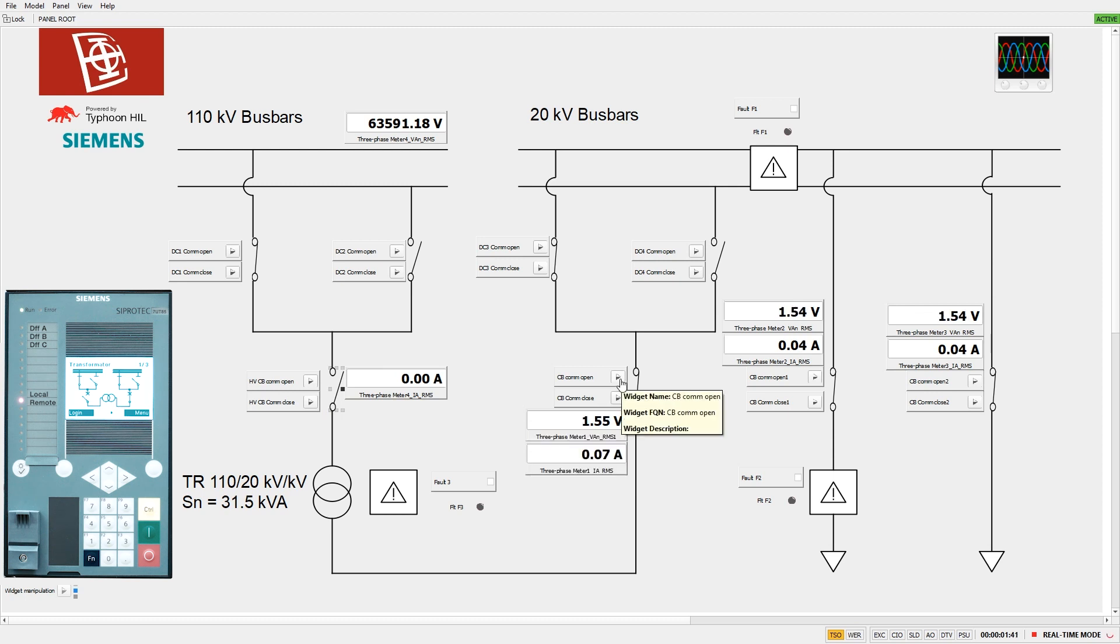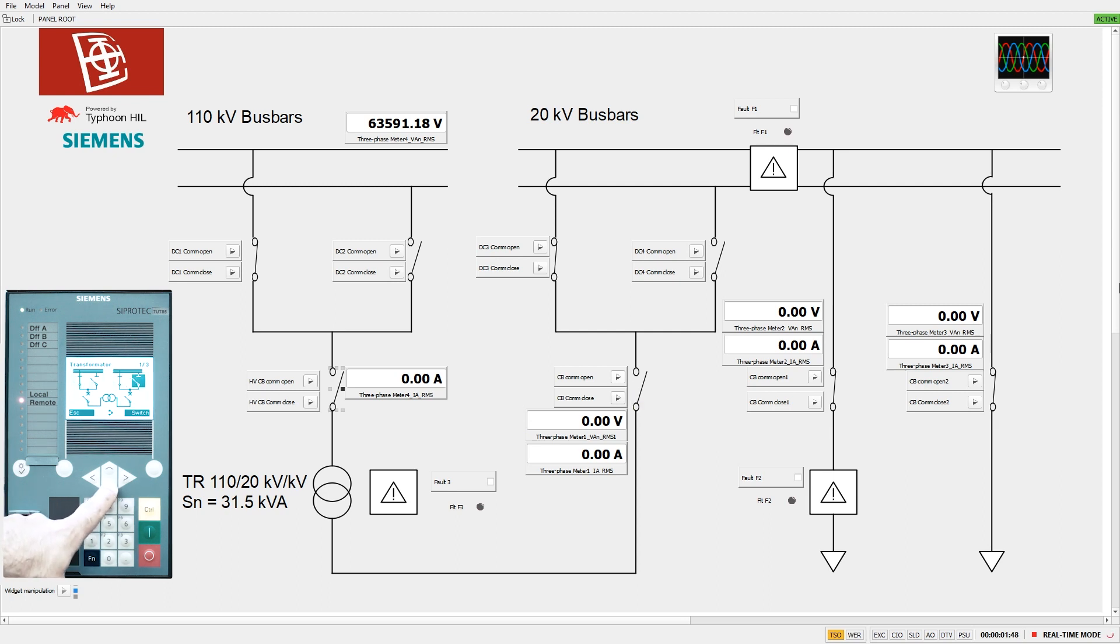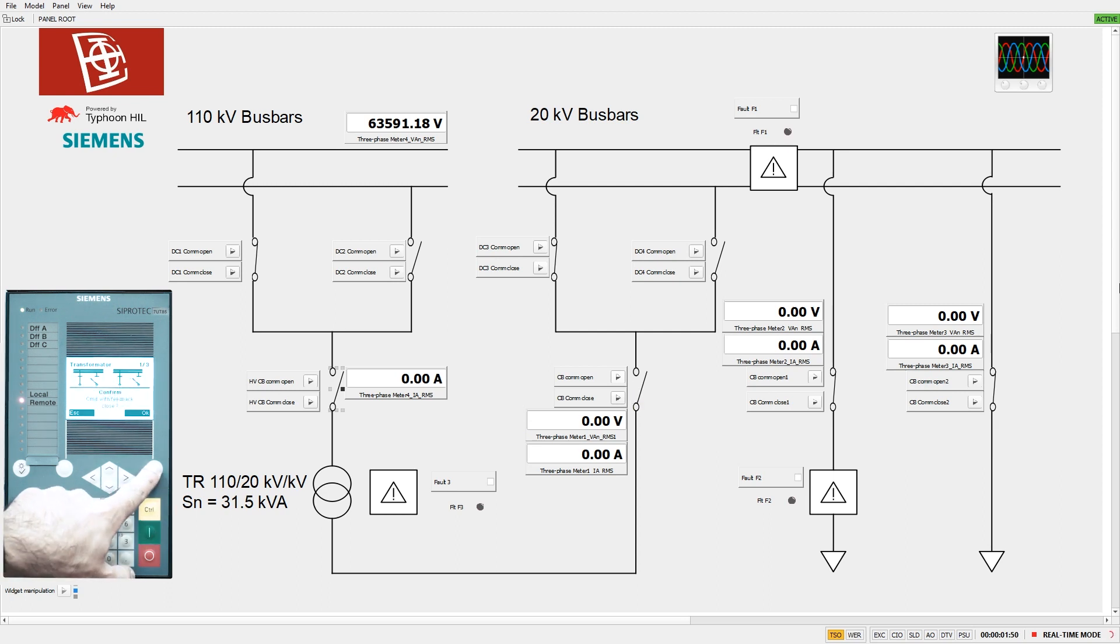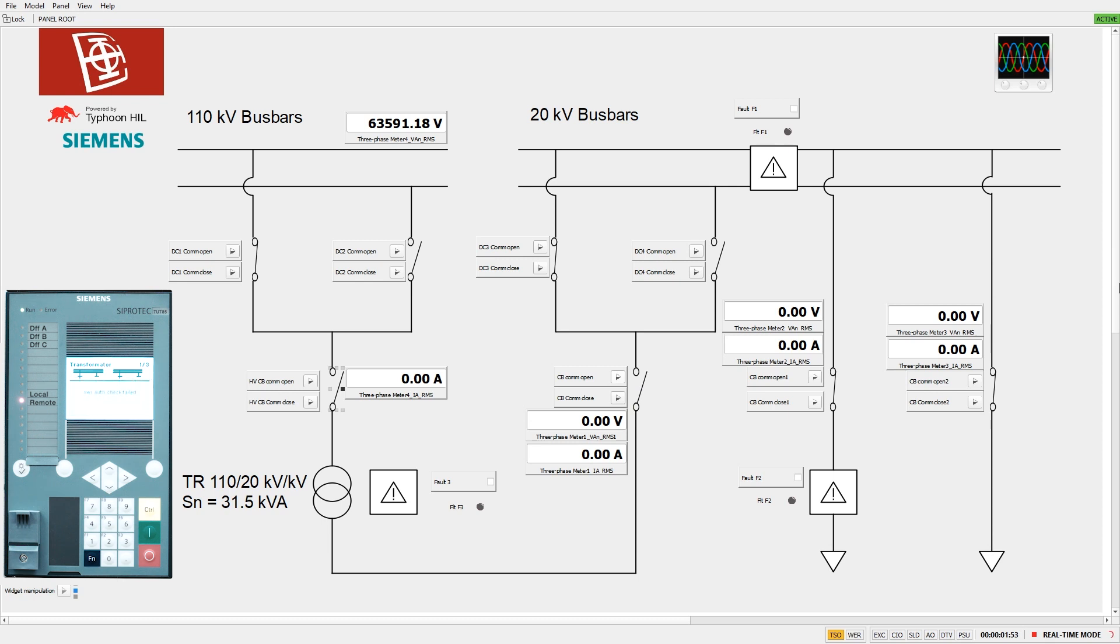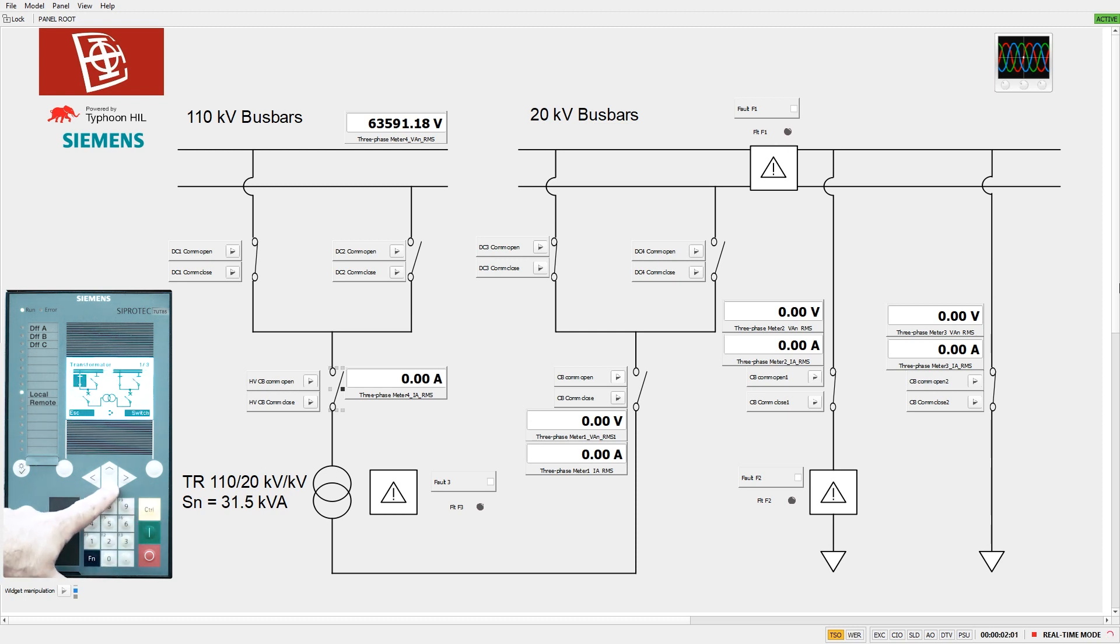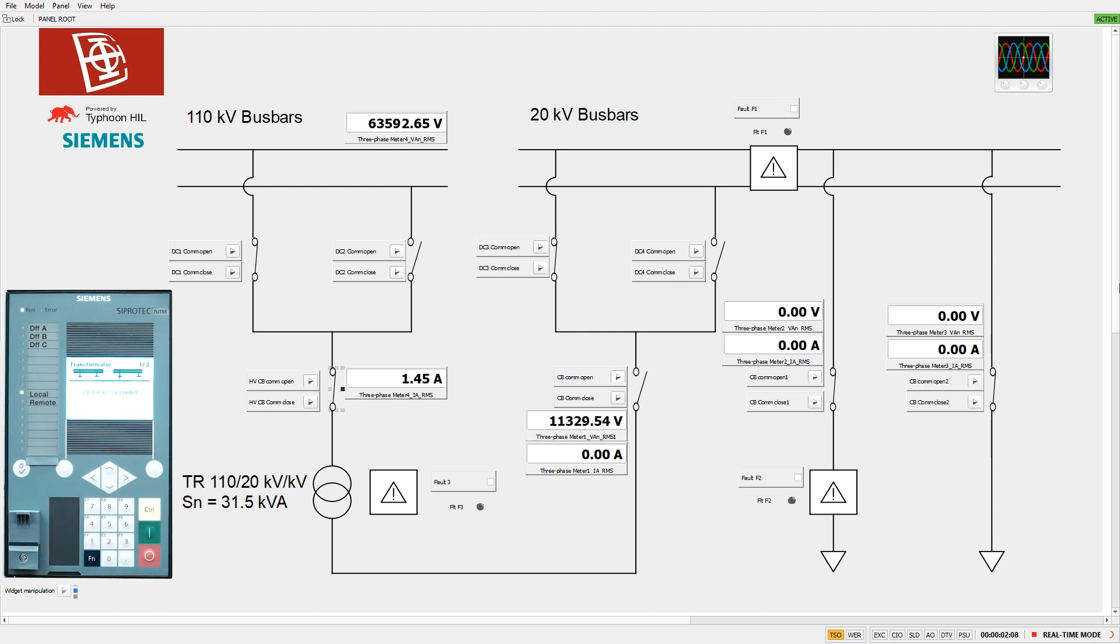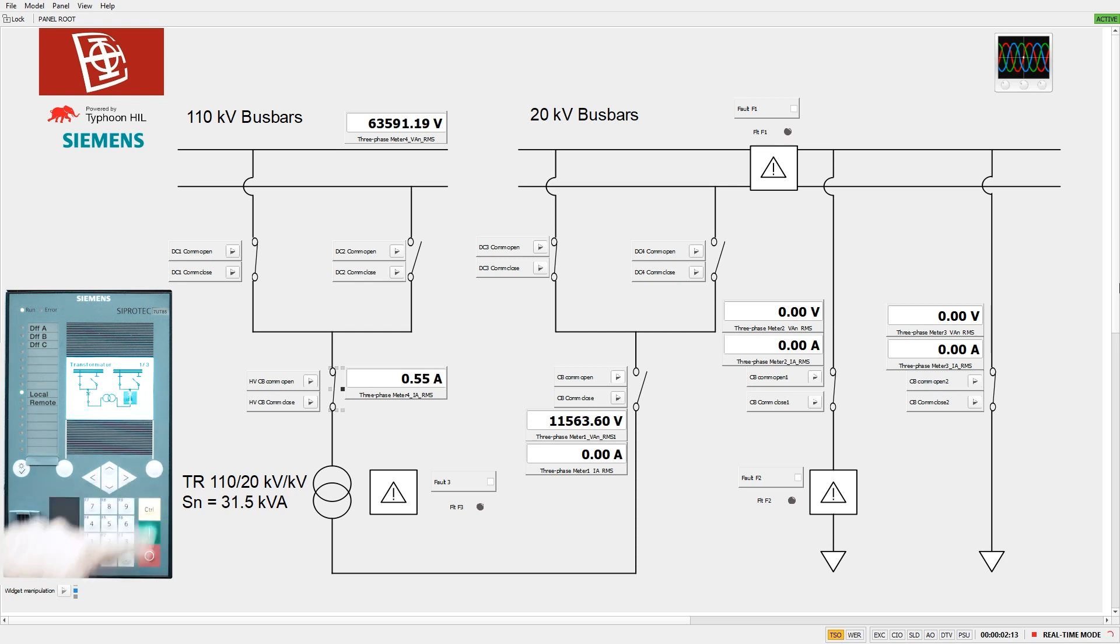Switching equipment such as circuit breakers and disconnectors can be controlled via the SCADA panel, the 6MU85 high voltage merging unit, the 6MU85 medium voltage merging unit, or the 7UT85 transformer differential relay. In order to be controlled by the 7UT85 differential relay, the device must be in local operation and the conditions for controlling the switching device must be fulfilled. The same applies to the two merging units.